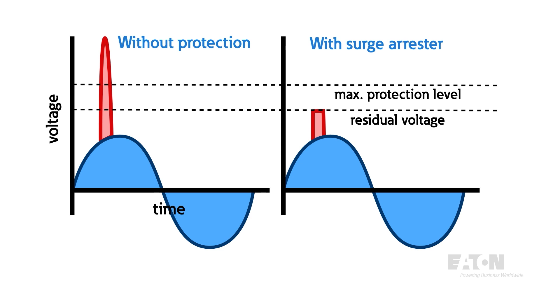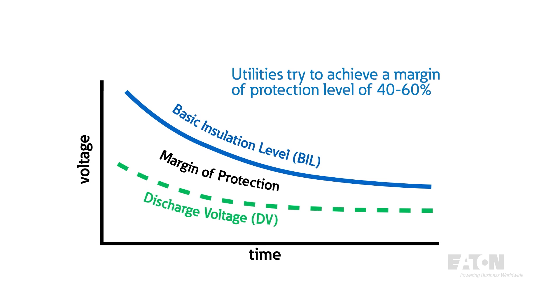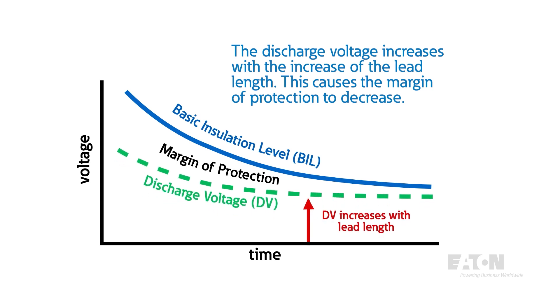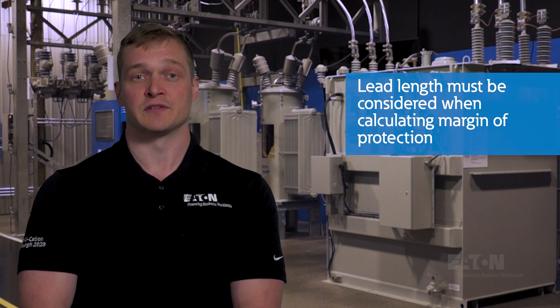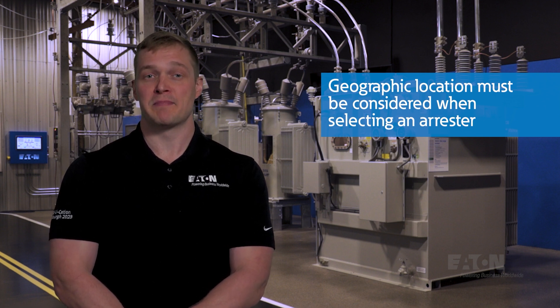Utility engineers need to ensure that the discharge voltage is lower than the basic insulation level, or BIL, of the protected equipment. The difference between these two values is known as the margin of protection. Every utility is different, but most try to achieve a margin of 40% to 60%. Like in residential applications, the lead length will affect margin of protection. Fast transients often have large voltage drops across conductors, so it must also be taken into consideration when calculating margin of protection.